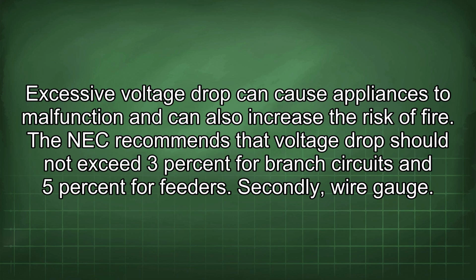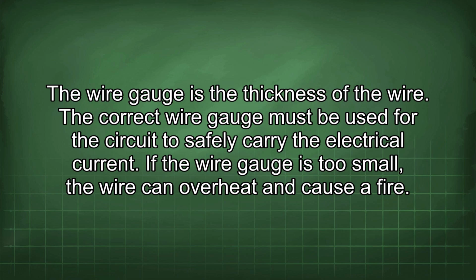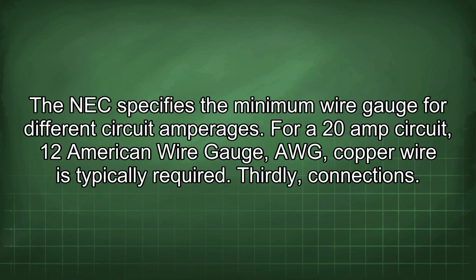Secondly, wire gauge. The wire gauge is the thickness of the wire. The correct wire gauge must be used for the circuit to safely carry the electrical current. If the wire gauge is too small, the wire can overheat and cause a fire. The NEC specifies the minimum wire gauge for different circuit amperages. For a 20-amp circuit, 12 American wire gauge (AWG) copper wire is typically required.